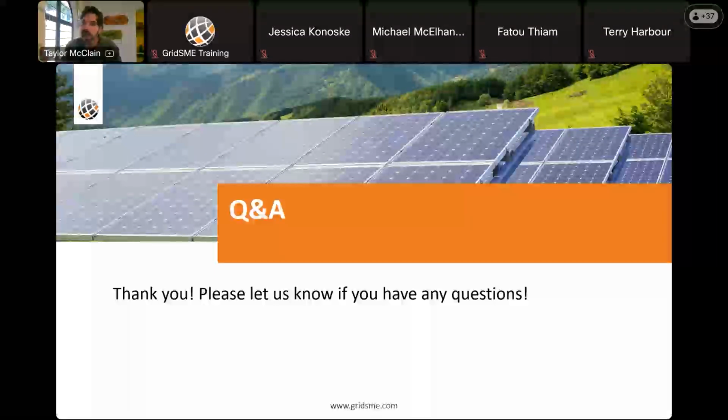Essentially, let me say it this way, projects that are in earlier clusters, if they continue to move through the generator interconnection process, their generation injection on the grid needs to keep being considered for future projects that come online. There are further breakdowns to be made between whether it's requesting full capacity or energy only or things like that. But to simplify things for this answer, if you have projects in Cluster 15, they are going to impact your Cluster 16 projects.